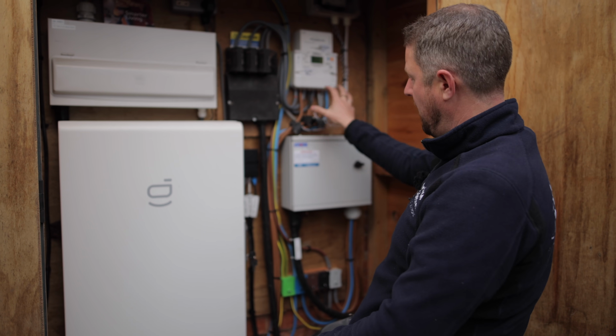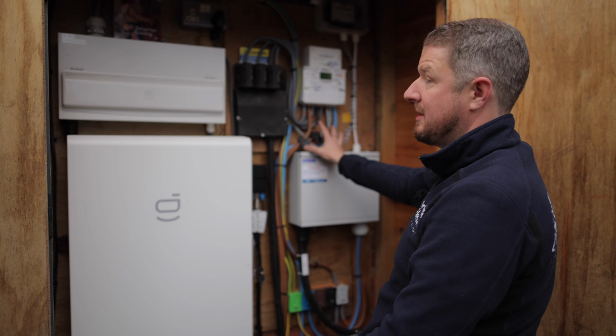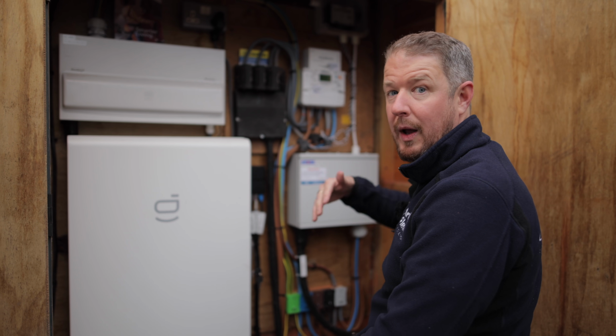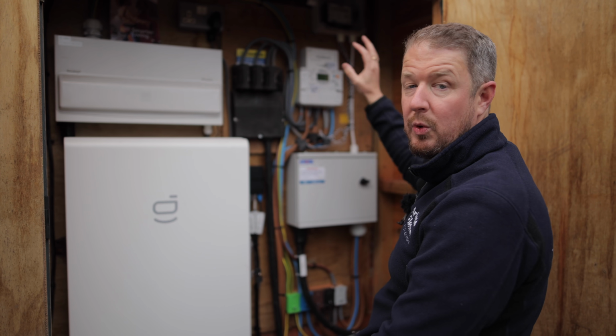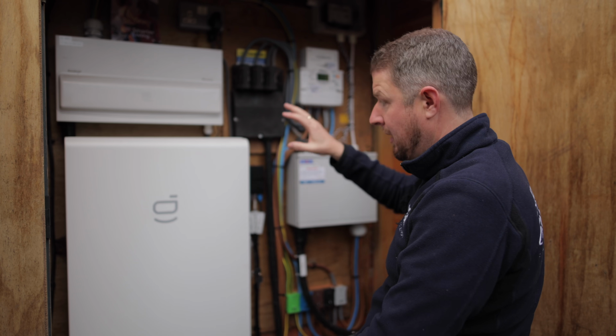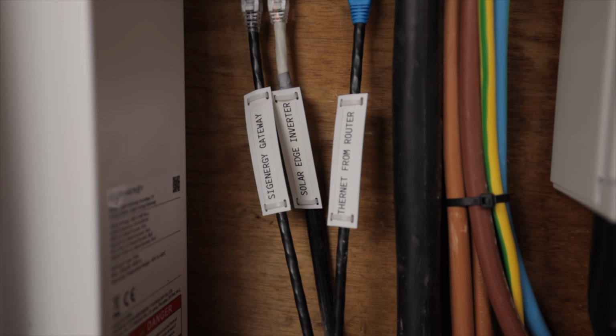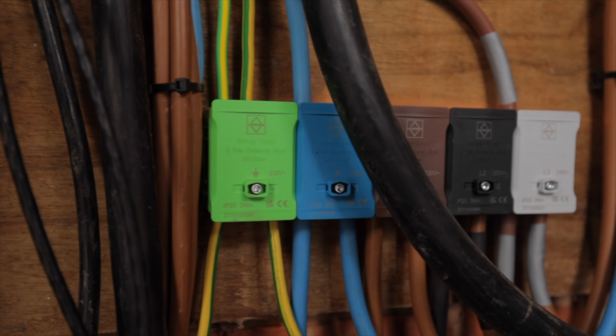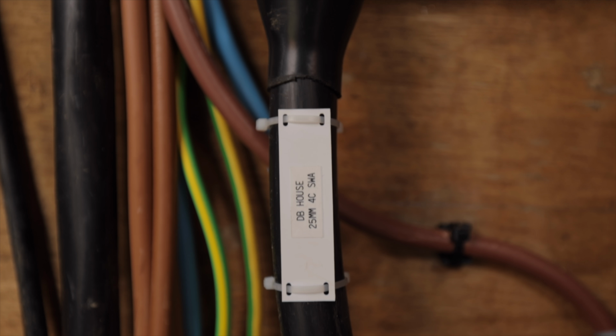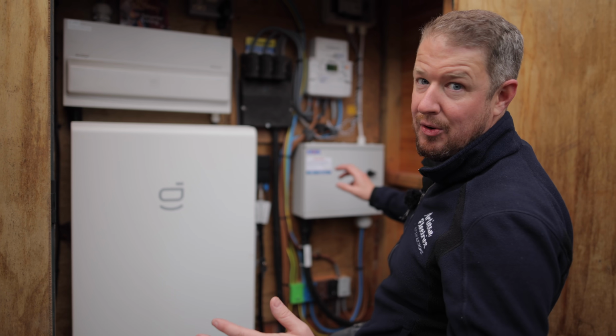We've given ourselves a 3-phase circuit for the SolarEdge Modbus. The SolarEdge Modbus with these CTs monitors how much power is coming in from the grid or going out to the grid, and it means we can also monitor things in the SolarEdge app as well as the Sigenergy app. It's all neatly connected together and ready to pump some beautiful power from the solar into this customer's house and even out to the grid.